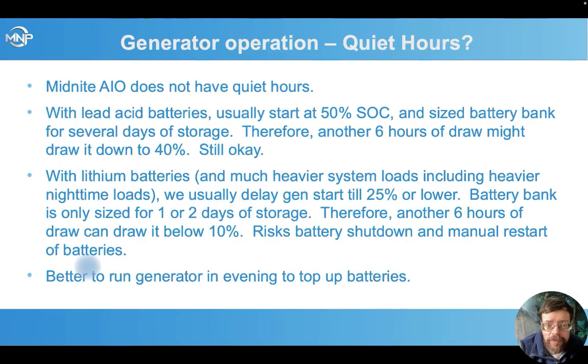So what I've seen with people using quiet hour programming on lithium batteries is they end up having shutdowns before morning, whereas with a lead acid system, you weren't playing it nearly as close to your absolute limit, so it made more sense. With these type of systems, it's better to run the generator in the evening to top up the batteries. If you see in your state of charge that you're not going to make it till morning without a generator run, just top it up in the evening rather than having it shut down overnight.